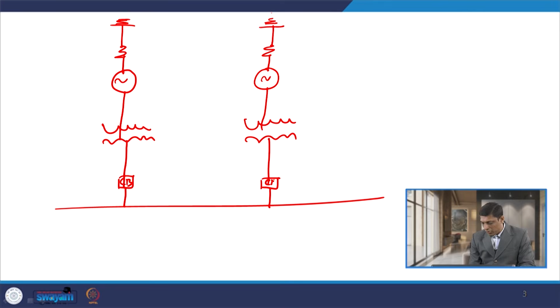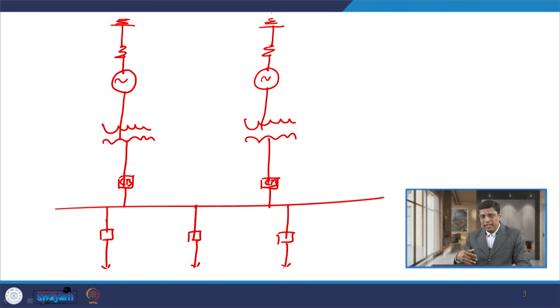So, now the question is how to overlap the protection zones. The location at which we place the CT, the current transformer, is going to decide the zone or overlapping zone of the different devices. For example, if I consider the line protection zone, then I connect the CT somewhere here. So, this zone is meant for the line. So, this is our line protection zone, right. Similarly, you can put a CT here and this is the line protection zone, you can put a CT here, this is the line protection zone.